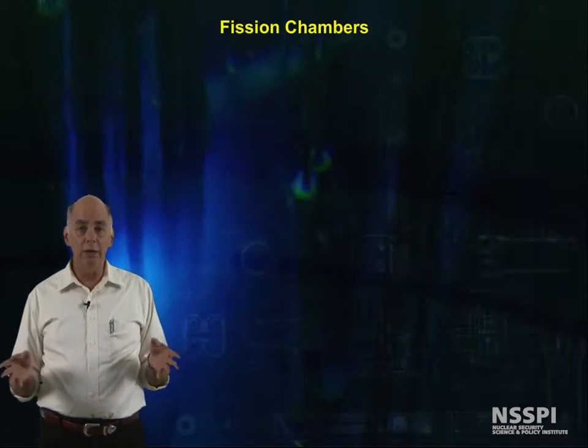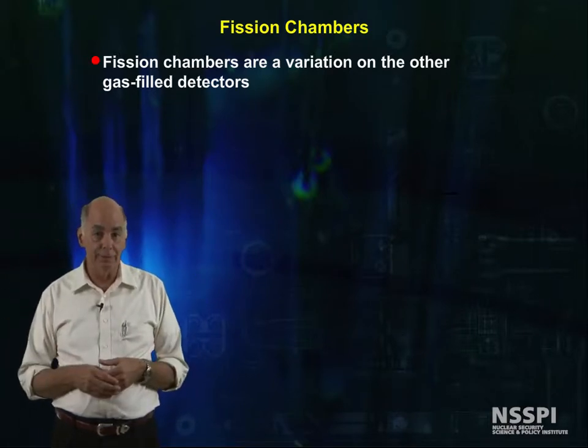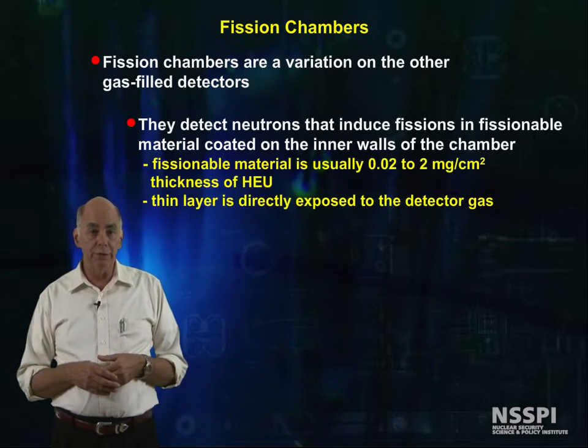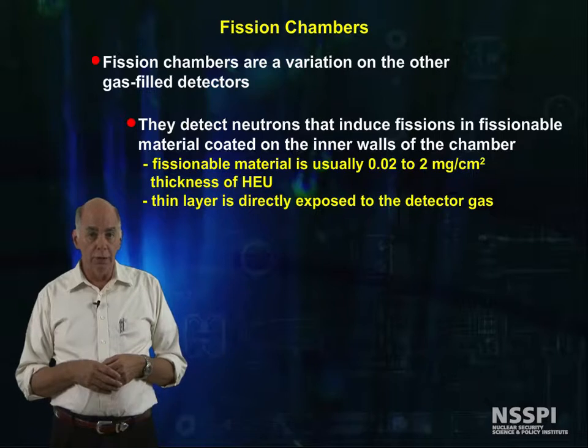Fission counters are widely used where you have lots of neutron signal, for example in reactors. They detect neutrons from induced fission of fissile material plated on the inner walls of the chamber. Usually this material is highly enriched U-235.